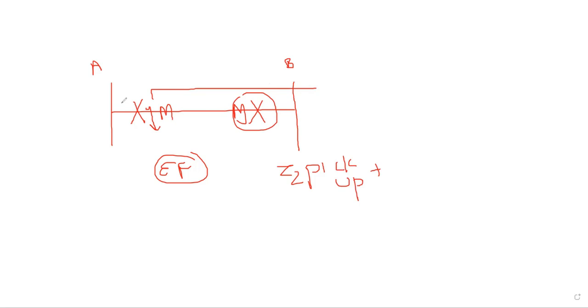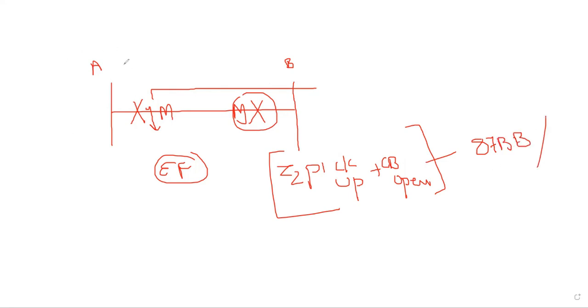Your line differential only you are explaining, right? Line distance, same. Okay. Zone 2 pickup and the breaker is in open condition. If these two conditions are there, then I am operating the busbar differential protection, 87 BB. This is the end fault protection. I am just checking that if my breaker shows zone 2 pickup and my breaker is in open condition, then I operate the busbar differential protection of this busbar, as a safety measure. This is the end fault protection.